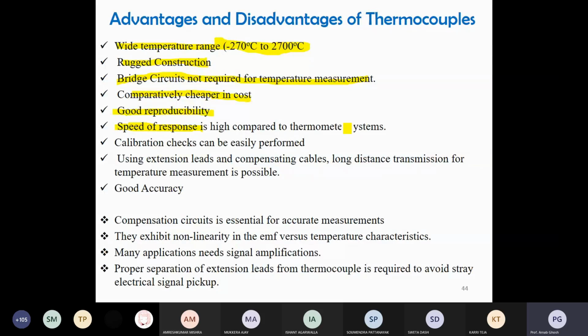Using extensions and compensating cables, long distance transmission for temperature measurement is possible. The thermocouple placed inside the boiler develops an electrical signal corresponding to the temperature, and this signal can be carried through an extension cord to be measured at your monitoring room.